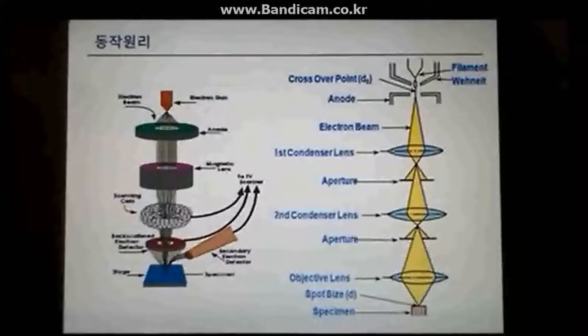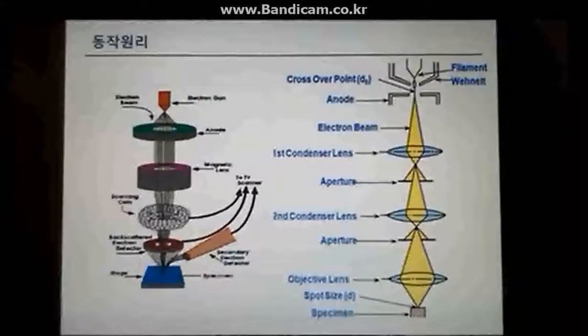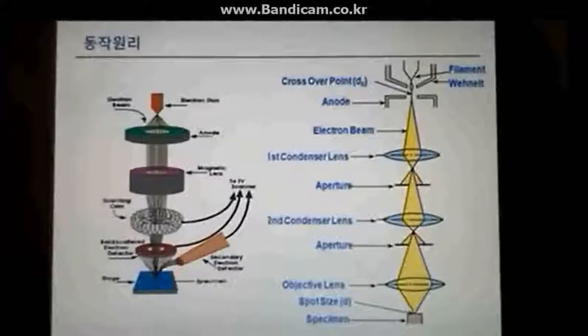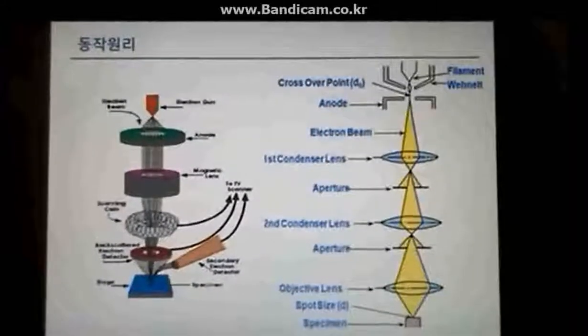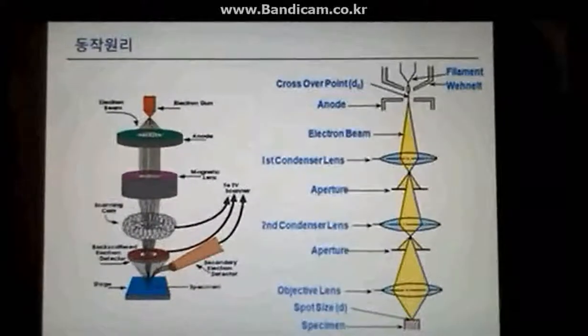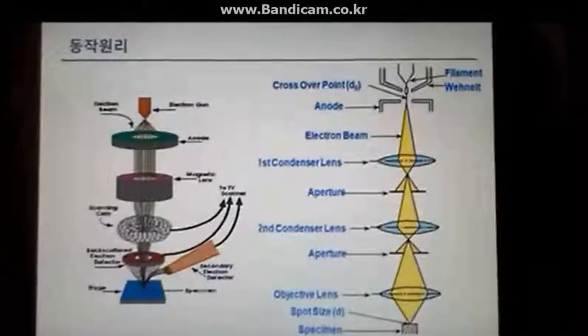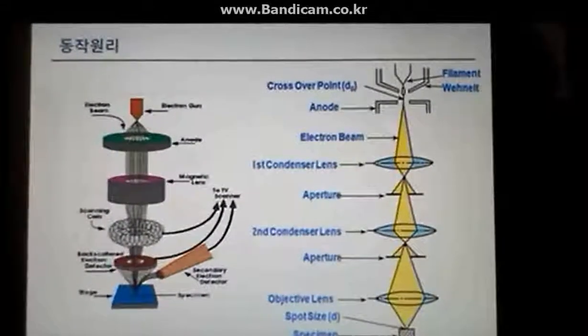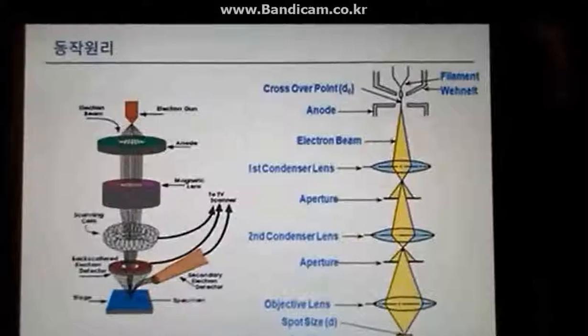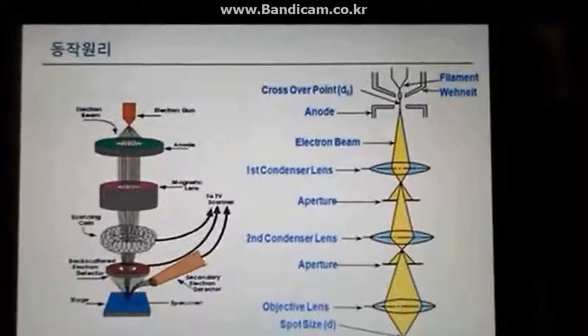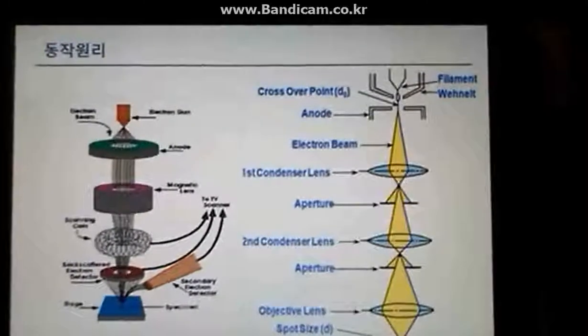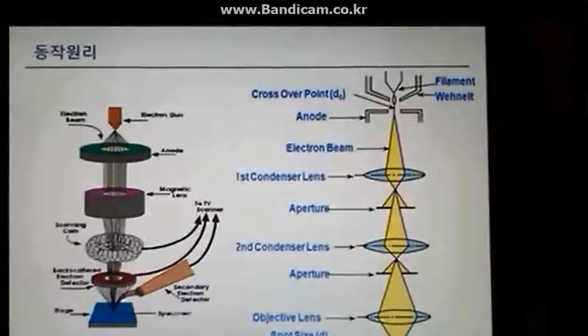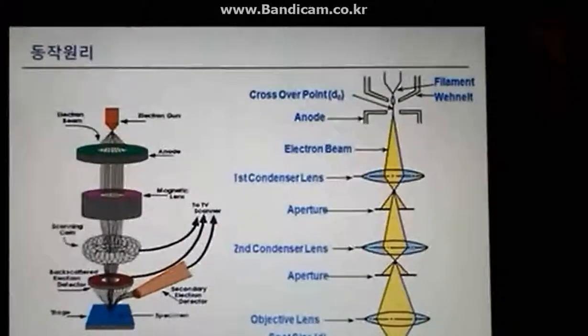The electron beam from the gun focuses on the condensing lens and goes through the objective lens to reach the sample. The condensing lens focuses the electron beam to make it small, whereas the objective lens places the electron beam at a desired position, accurately directing the beam to the observing position.